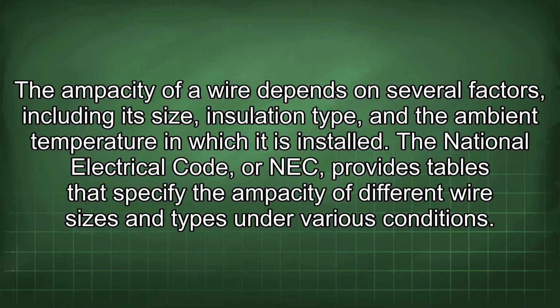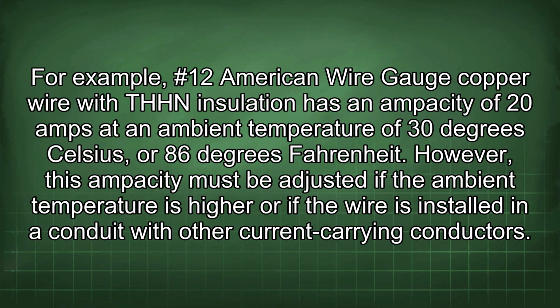The National Electrical Code, or NEC, provides tables that specify the ampacity of different wire sizes and types under various conditions. For example, #12 American wire gauge copper wire with THHN insulation has an ampacity of 20 amps at an ambient temperature of 30 degrees Celsius or 86 degrees Fahrenheit. However, this ampacity must be adjusted if the ambient temperature is higher or if the wire is installed in a conduit with other current carrying conductors.